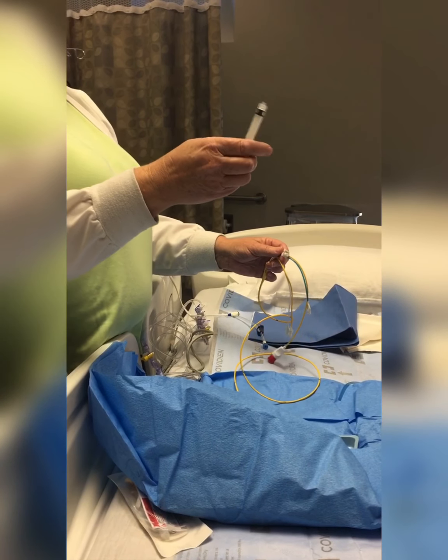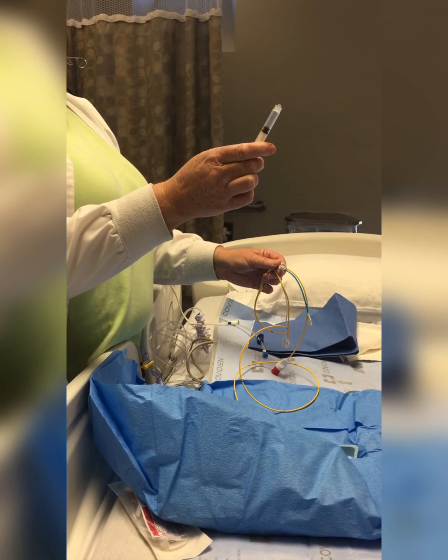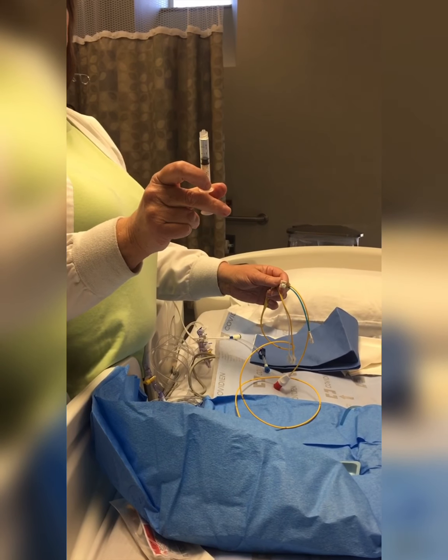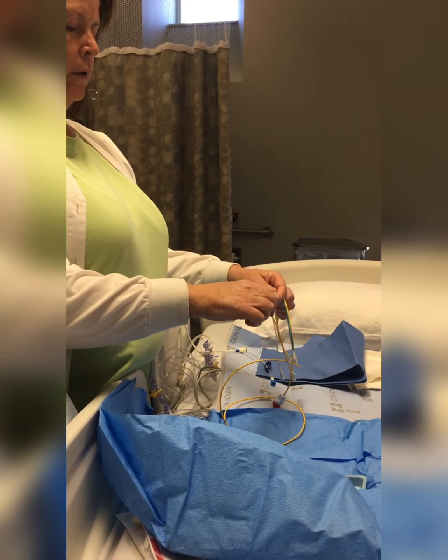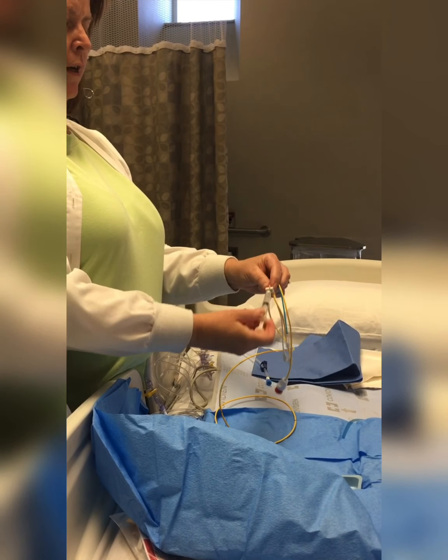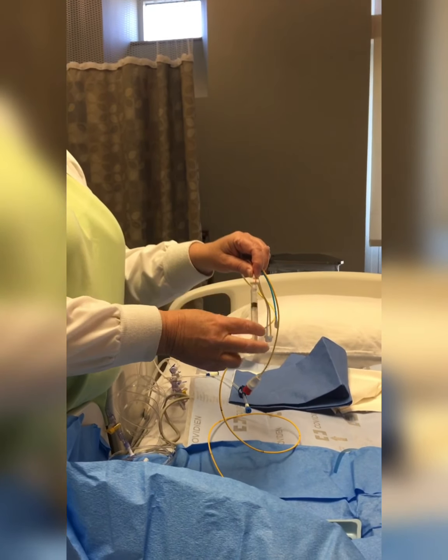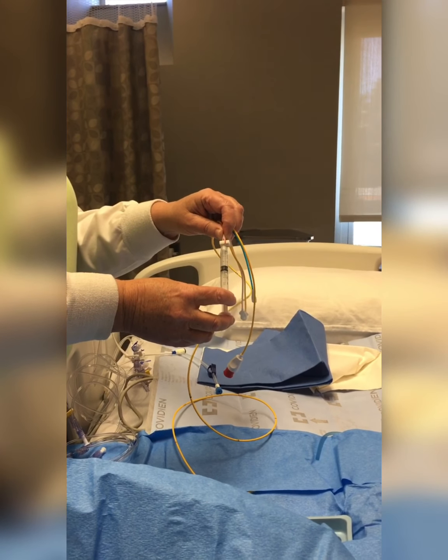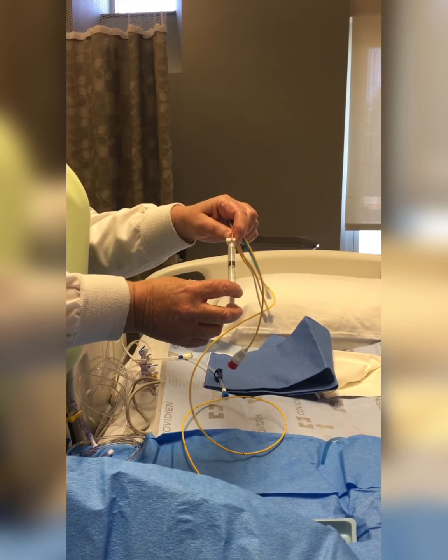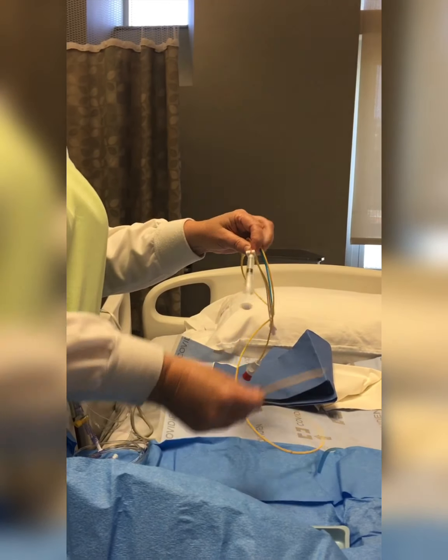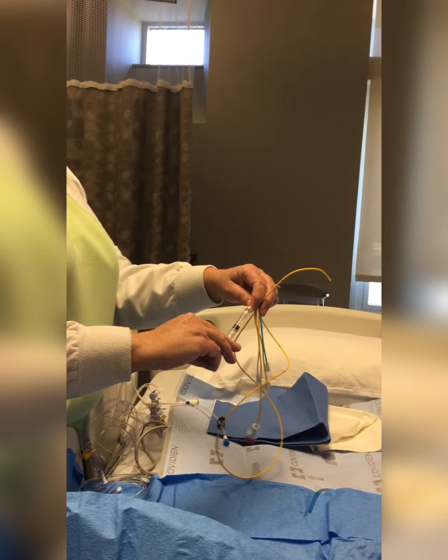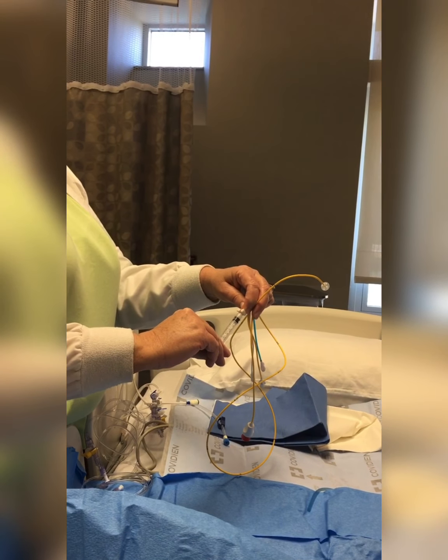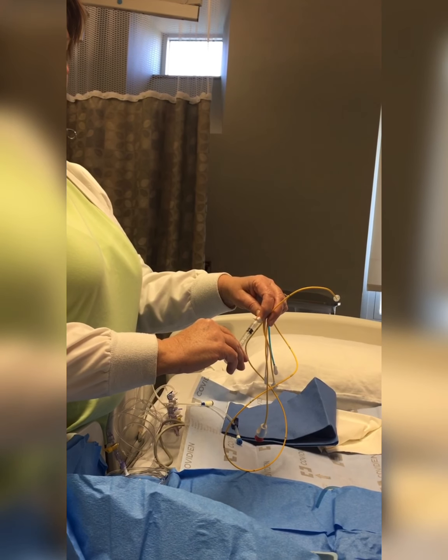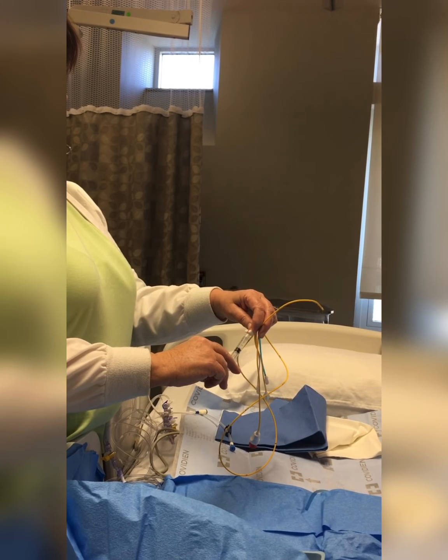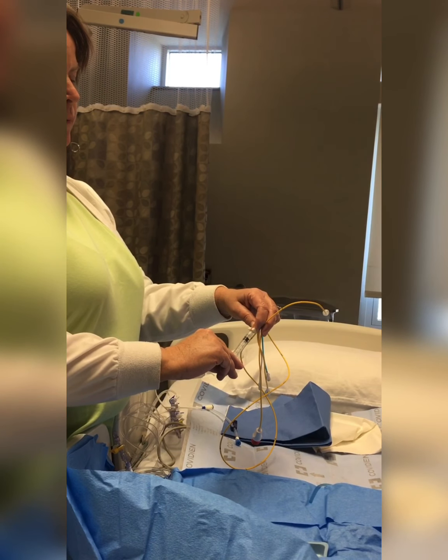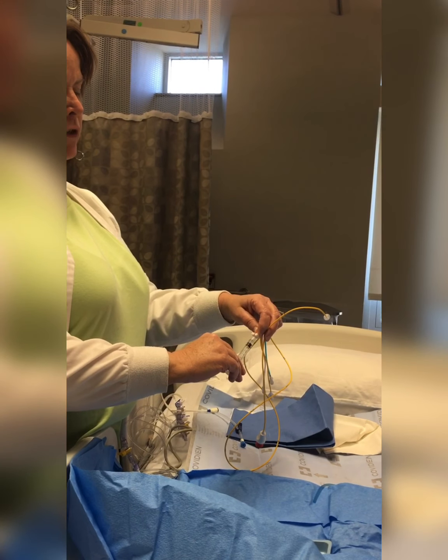So here's your little syringe, and you open it up, and it can only hold 1.5 cc's of air. It goes on here. That way you don't overinflate your balloon, and it has a little red line right here. See the red line that says that the balloon is locked? When you're ready to inject the balloon, you push it back and the line is straight. And if you look at the end, we're going to push the balloon up. There's the balloon. And you let it go, and it goes out all on its own. Don't push too hard. You're just going to push slow and easy, because the balloon with too much pressure too fast could break.